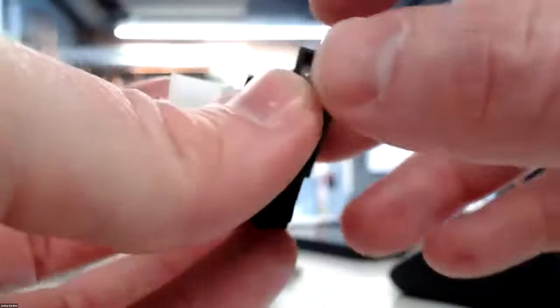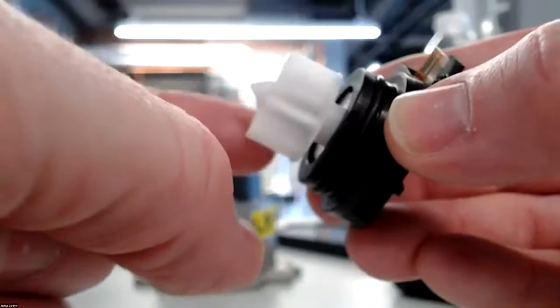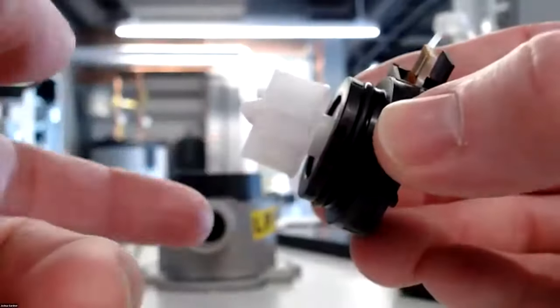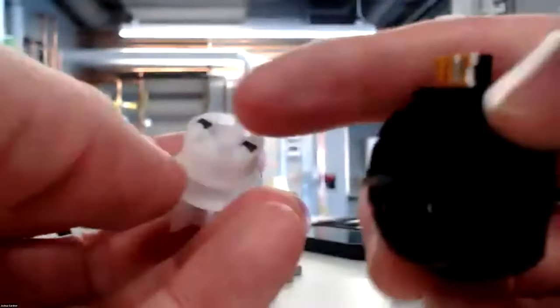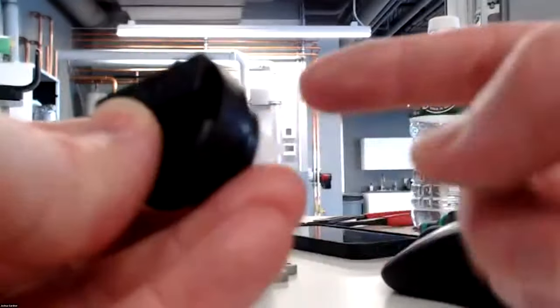This is the flow sensor. You'll take it, pull it straight out. Wiring connections right here. And this is the flow wheel, okay? So this will just move. There's no screens in there. Two little magnets on here. It'll move against the control inside, and that's what will give us our flow rate. And we'll be able to see that flow rate in live time on the control as well.